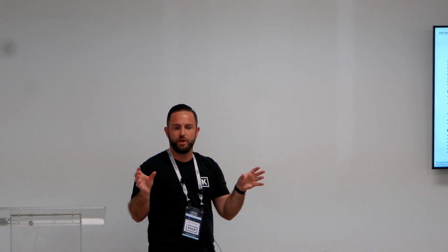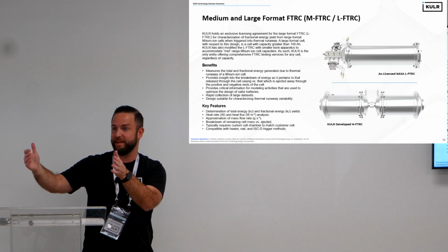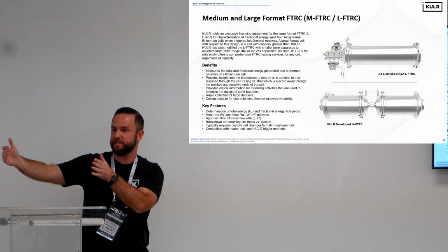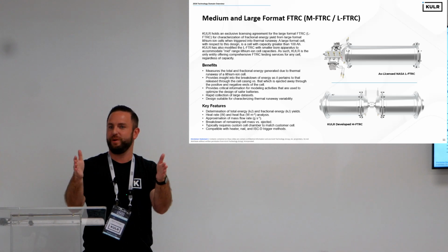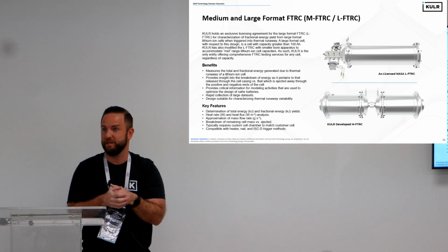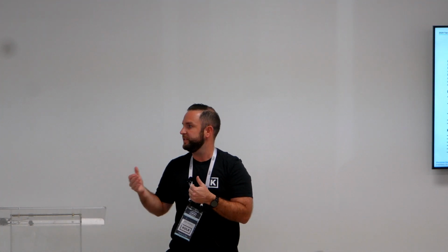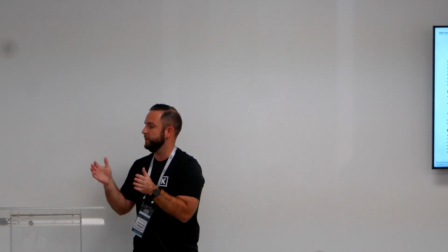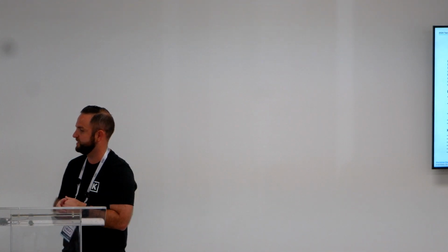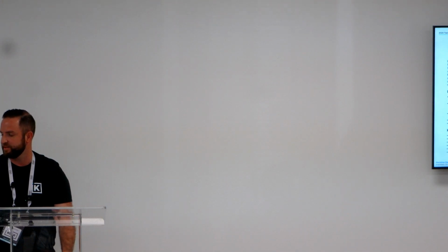So you kind of have a big jump, right? If you're in the small calorimeter and you're testing cells up to 10 amp hours in capacity, then you've got this big calorimeter that can test cells that are above 100 amp hours in capacity. Well, there's a big range between 10 and 100. What do you do with those cells? Because there's a lot of those cells used in industry today too. So we modified the design to be modular such that we could scale it down in size to allow us to test what we call mid-format cells.